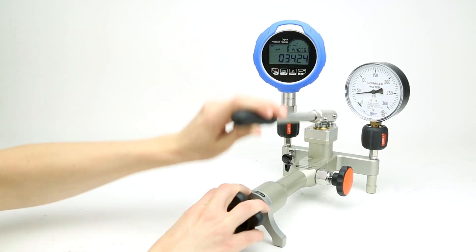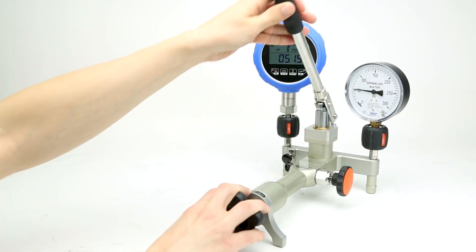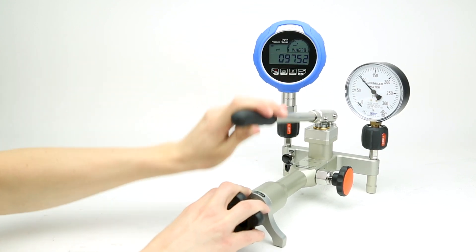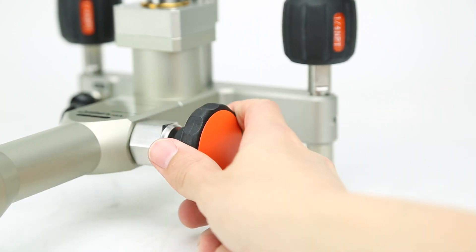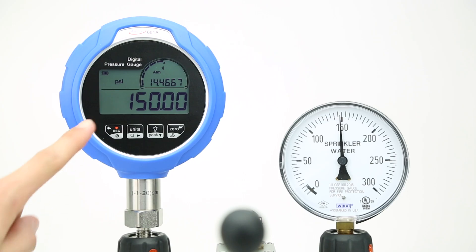After making note of the zero point on each gauge, operate the pump until the reference gauge reads your second set point, in this case 150 psi. To get an exact reading, you may need to close the isolation valve of the pump and use the fine adjust knob instead of the lever arm. Once you record the readings from both gauges, continue through the set points, going up to 300 psi and then back down to 150 and finally to zero to finish the test.